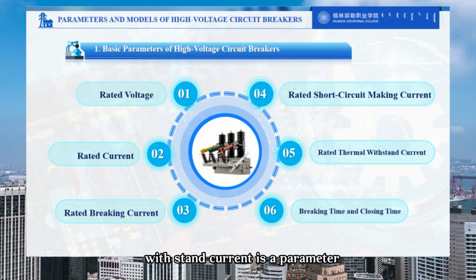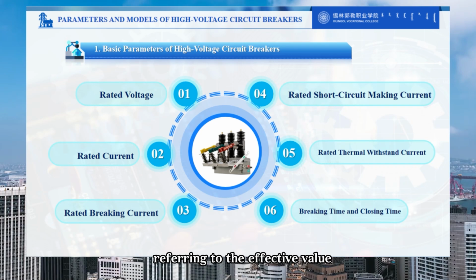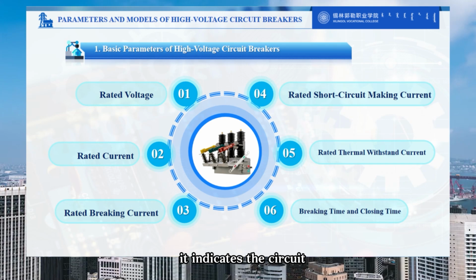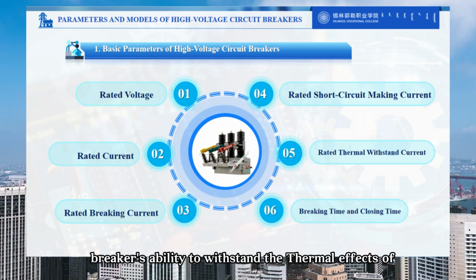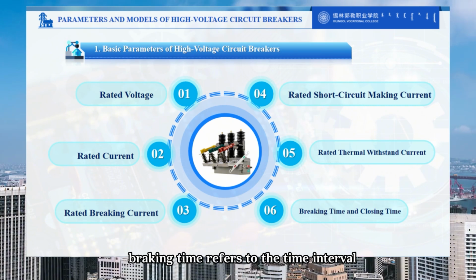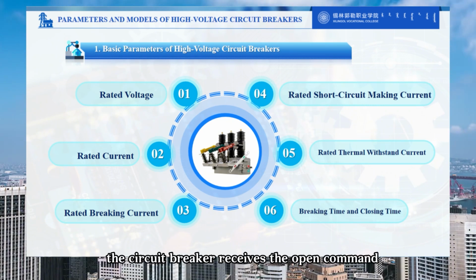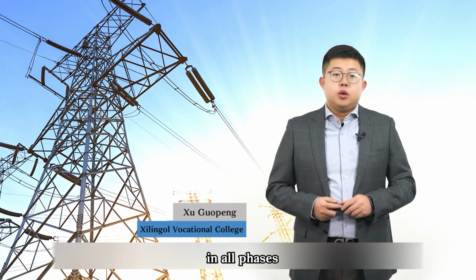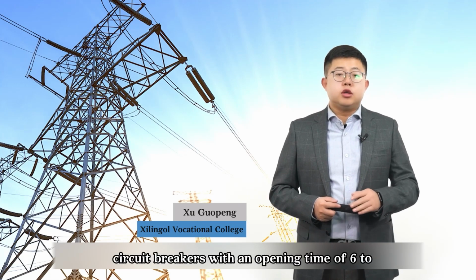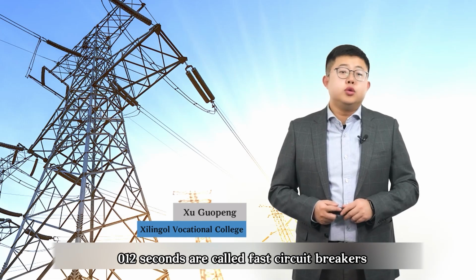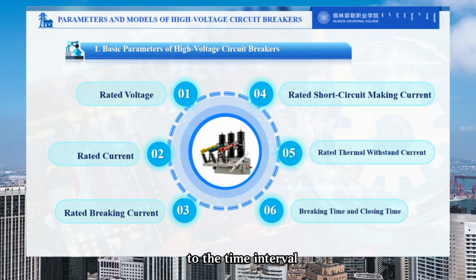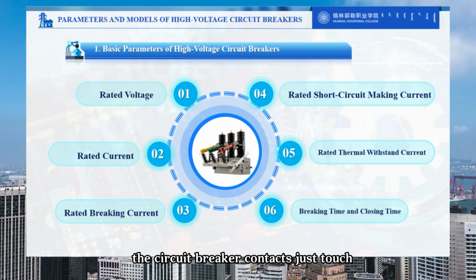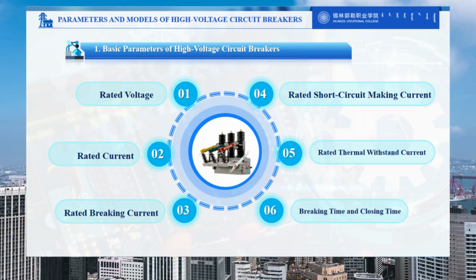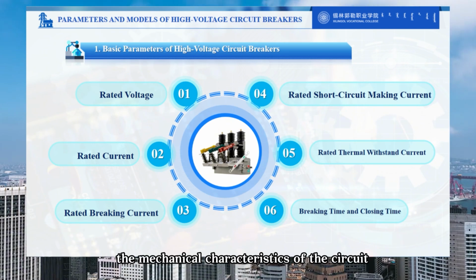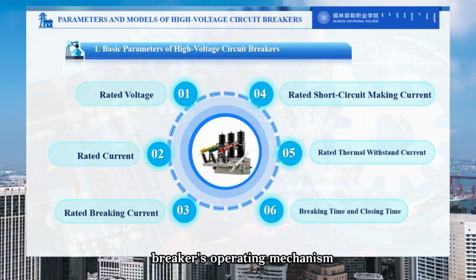Rated short time withstand current is a parameter referring to the effective value of the maximum current that the circuit breaker can allow within a specified time. It indicates the circuit breaker's ability to withstand the thermal effects of short circuit current. Breaking time refers to the time interval from the instant the circuit breaker receives the open command until the arc is completely extinguished in all phases. Generally, circuit breakers with an opening time of 0.06 to 0.12 seconds are called fast circuit breakers. Closing time refers to the time interval from when the closing circuit is energized until the circuit breaker contacts just touch. The length of the closing time depends on the mechanical characteristics of the circuit breaker's operating mechanism and intermediate linkages.